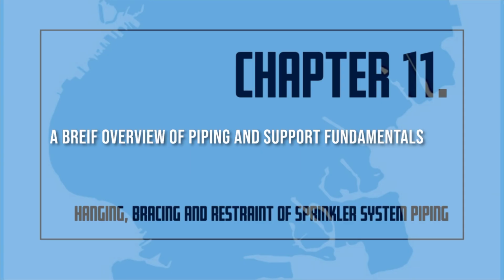There are extensive additional hangings and bracing requirements for CPVC piping, and the installation and design manuals for this product must be referenced to perform adequate visual inspections required by the standard. The distance for the hanger assembly to the center line of an upright sprinkler head shall not be less than 3 inches. Hangers placed closer to sprinklers will cause an obstruction to the discharge pattern.